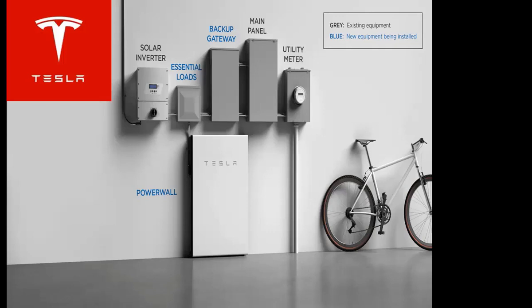We had no monitoring back then. So we had to send a technician, roll a truck out to the homeowner's house, of course, and then take our multimeter and test each individual panel along with the BOS system, the balance of system, the solar inverter, all of the things that are tied to that particular power plant. Took a lot of time. Took a lot of resources. But as time went on, with the use of internet and cloud management systems, we now have the ability, from our home office, along with the homeowner as they're traveling via their smartphone, to literally hit an app on their phone and zoom in and actually see what their power plant is producing, what they're consuming, and then what their net is.